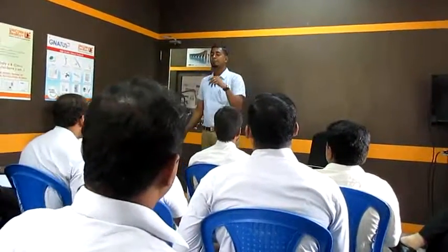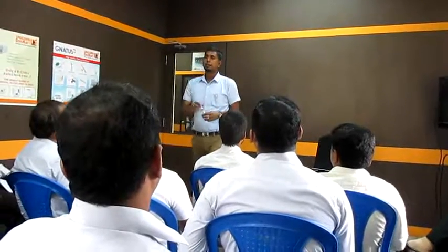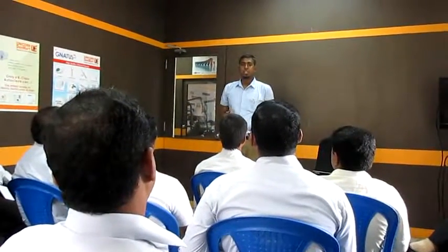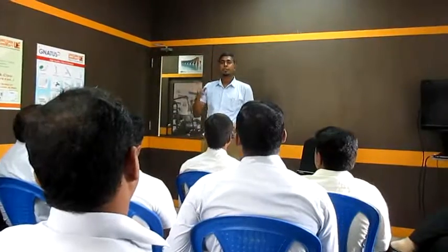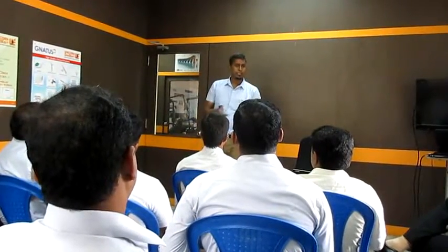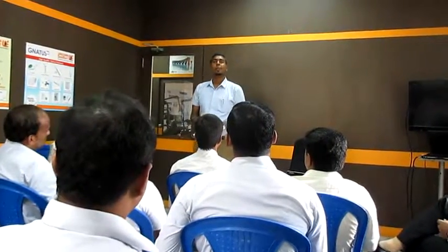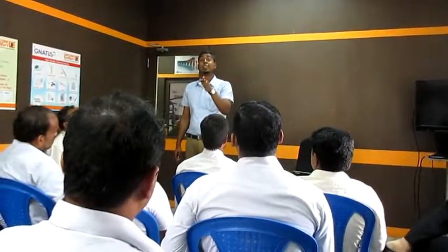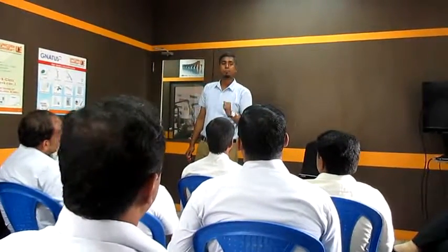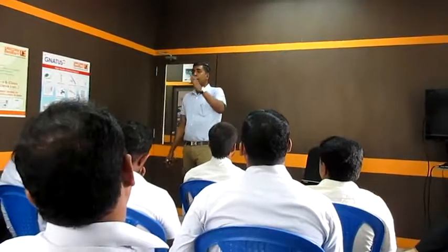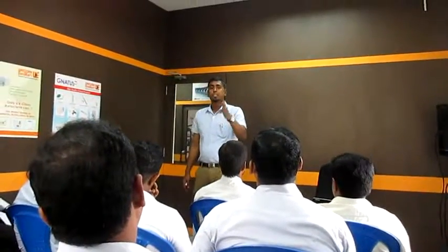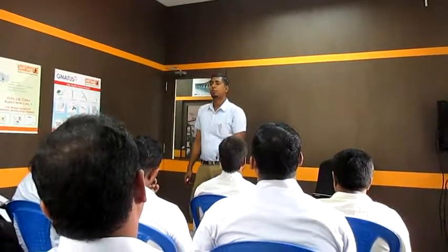Now you will say, sir, if a 70 kV machine becomes 72, or 60, does it mean the machine has failed? No. AERB has set guidelines for the deviation of these parameters. For example, AERB said that for kVp, plus or minus 5 kVp is allowed.